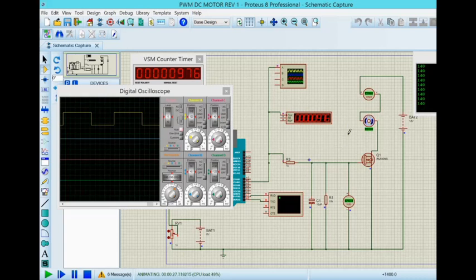So that's part of the control process that you need to ensure that you understand, that when you put your parameters for the constant required for your control output, you have to build in the fact that this has some kind of slow response. Now it's going to 142, spinning faster. The amps stay there. If I increase this more, 146, that's basically it, 83, almost 1 amp.